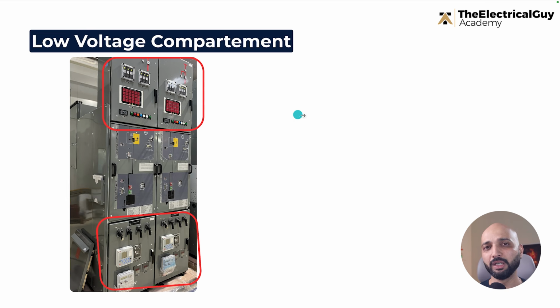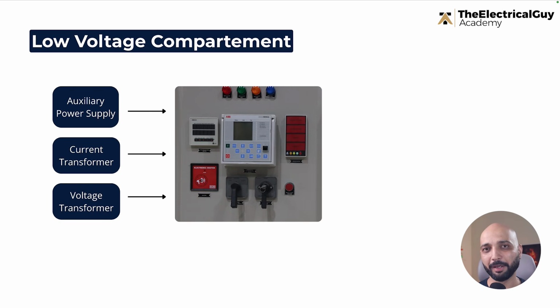Now the question is, how do we get the supply here? First, the most important thing is the auxiliary power supply. We talked about this, right? So 110 volt DC, 220 volt DC, that is the auxiliary power supply, and that will be inside the site or on the site. There will be maybe a battery bank or a dedicated auxiliary transformer which steps down the voltage and converts it into DC if it's working on DC, and then everything is fed from the auxiliary power supply: indication lamps, relays, and things like that, right? That's one input for the low voltage box.